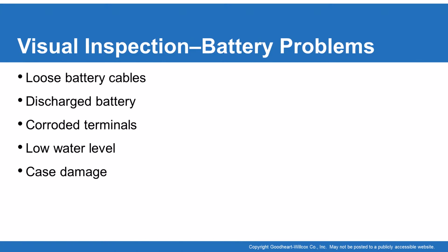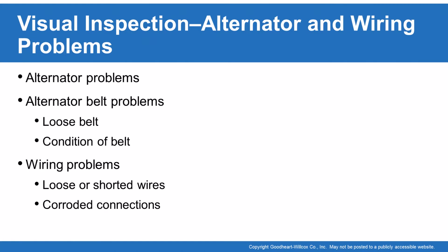We also want to take a look for corrosion on terminals that'll create high resistance, low water level on those maintenance style batteries. Today, most batteries say are maintenance free. And then we want to look at the case. Look at that case and see if the actual battery case itself looks like it's swollen or bloated, which in many cases indicates that something internally is going bad with the battery or overcharging might be happening.